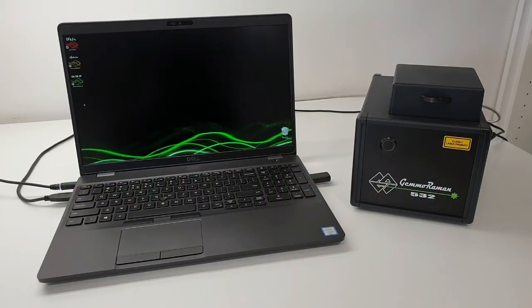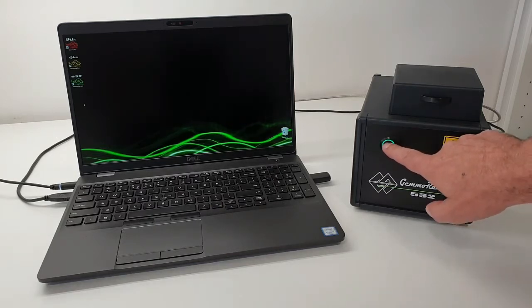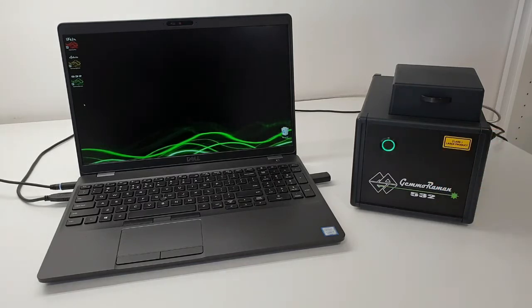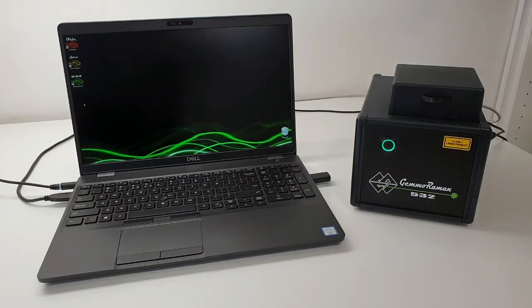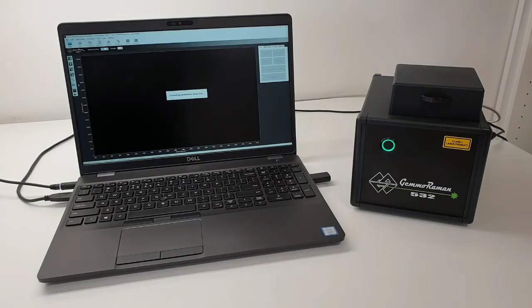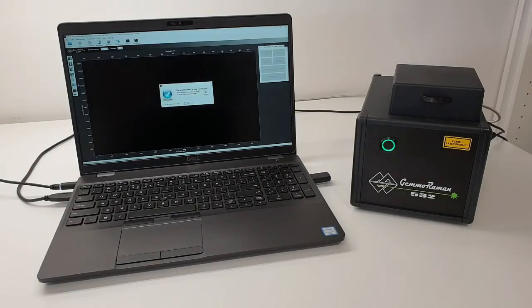Calibration and Raman scanning. Switch on the computer and then press the power button on the Raman front panel. Double-click on the Raman icon on the computer's desktop. Once the software starts, you will hear a click sound coming from the Raman. It's the shutter of the laser performing an opening test.